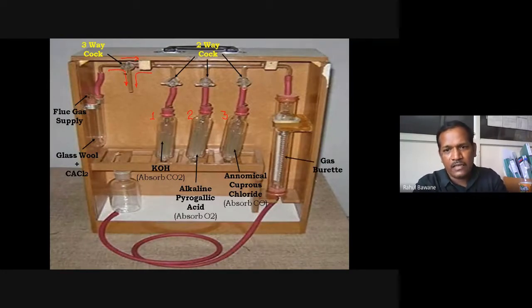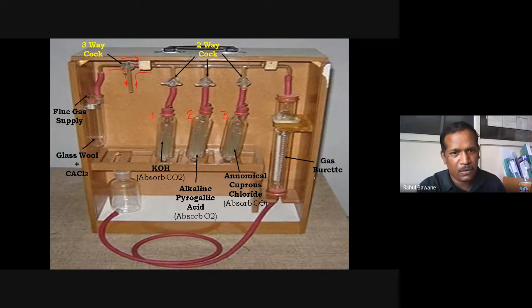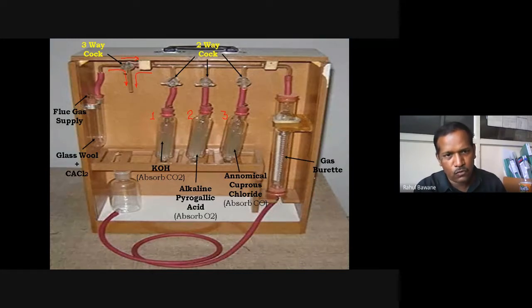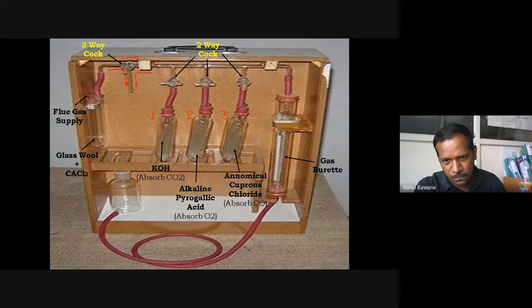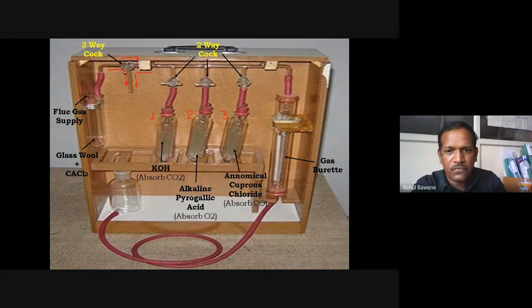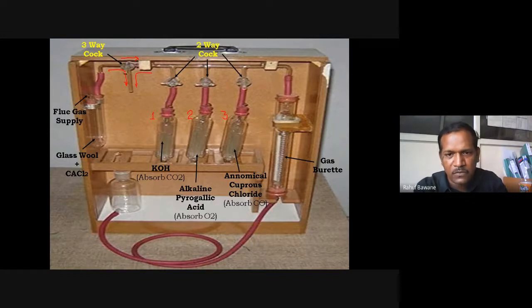The next part of the apparatus is the gas burette. Whatever flue gas sample we are supplying for analysis should be a known volume. So we allow a known volume for analysis. The gas burette is calibrated so we know how much gas is present. Outside the gas burette there is a large glass tube filled with water, serving as a water jacket.